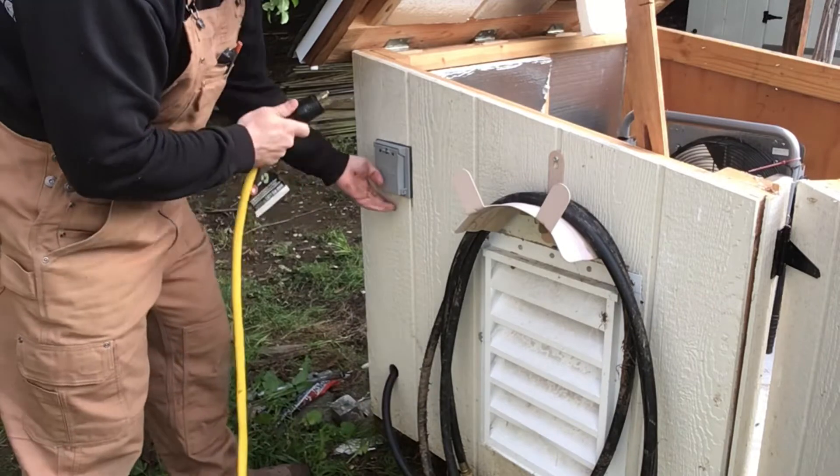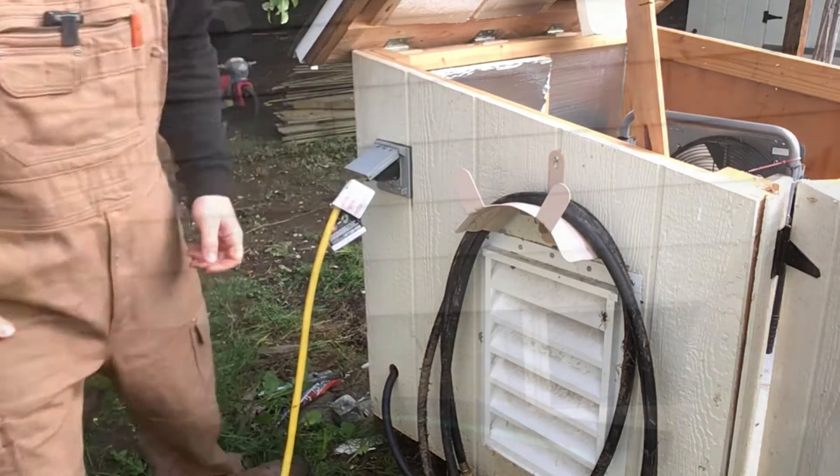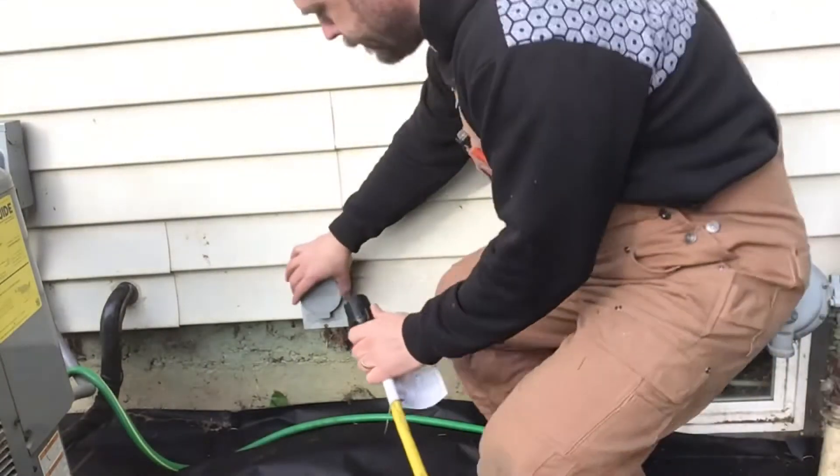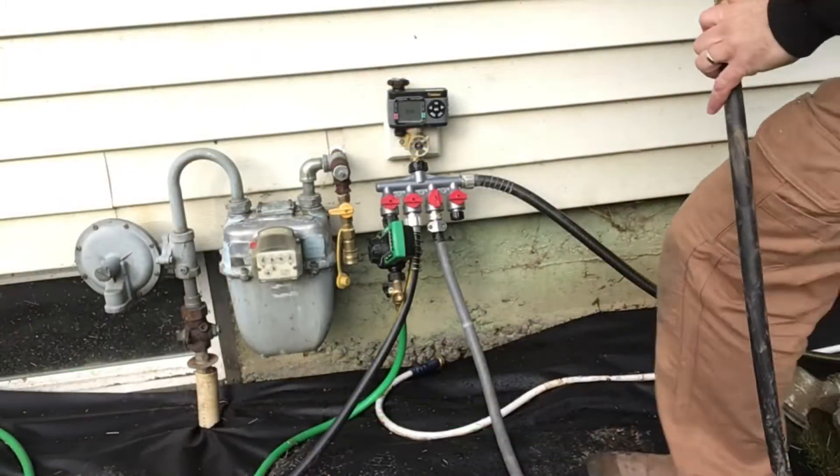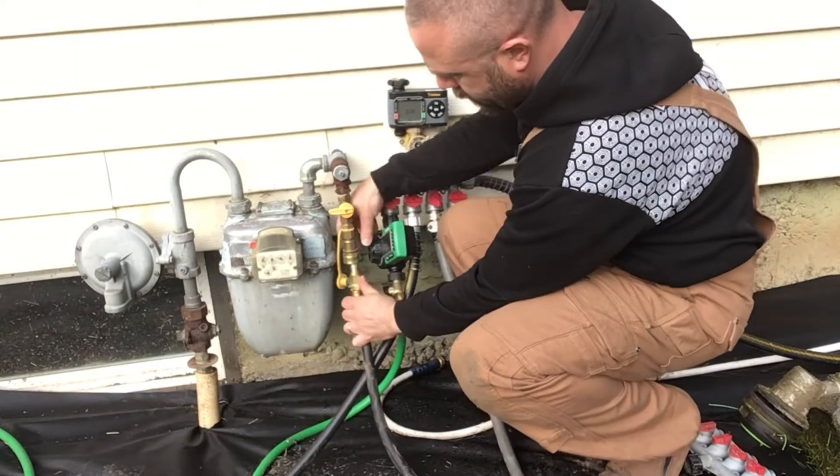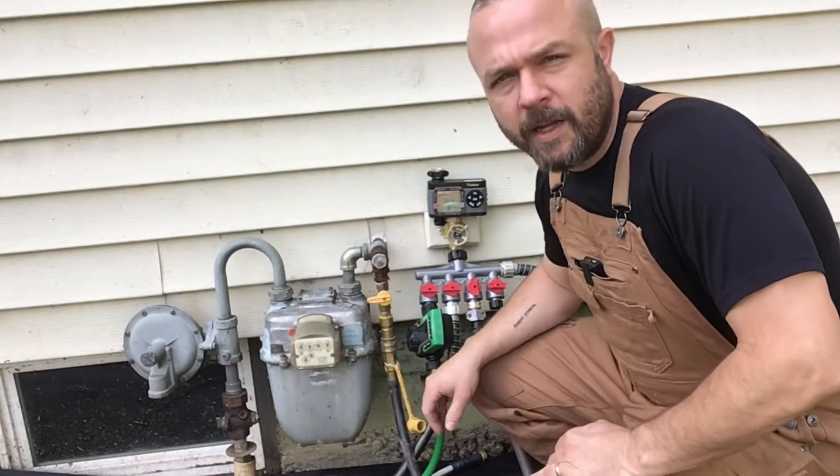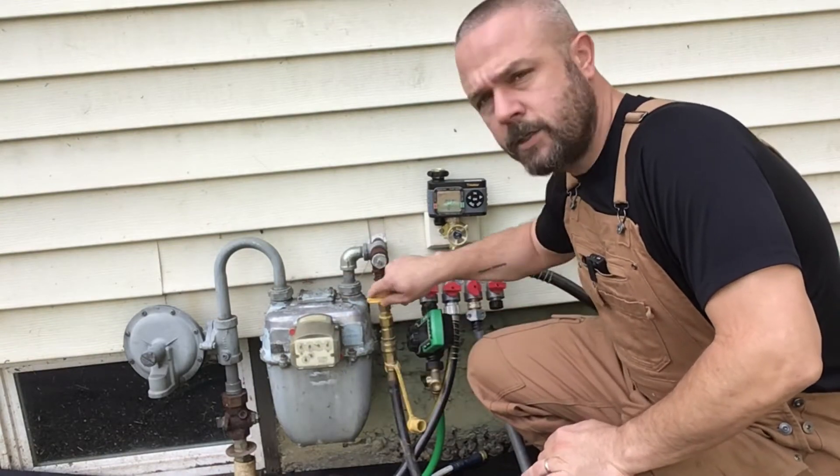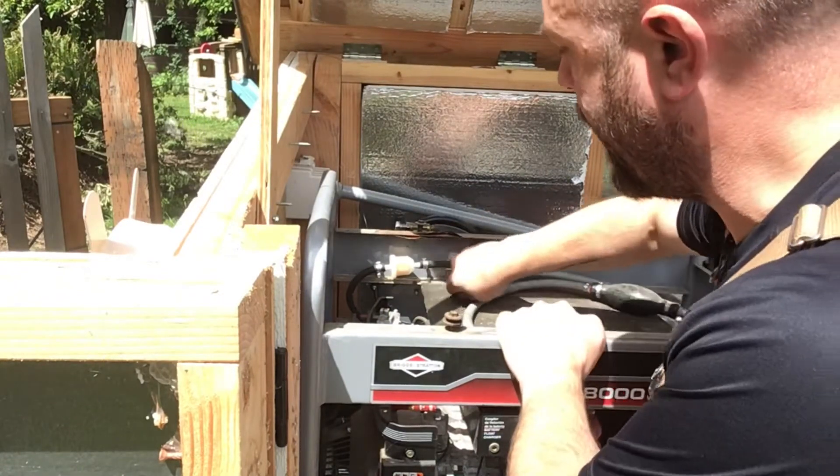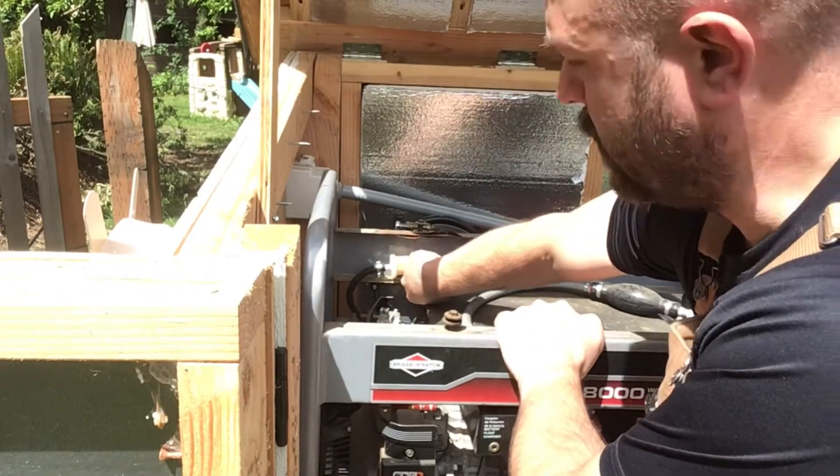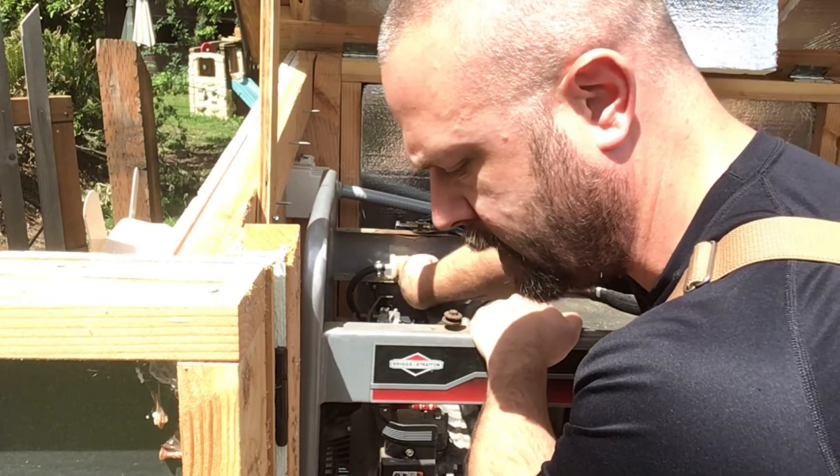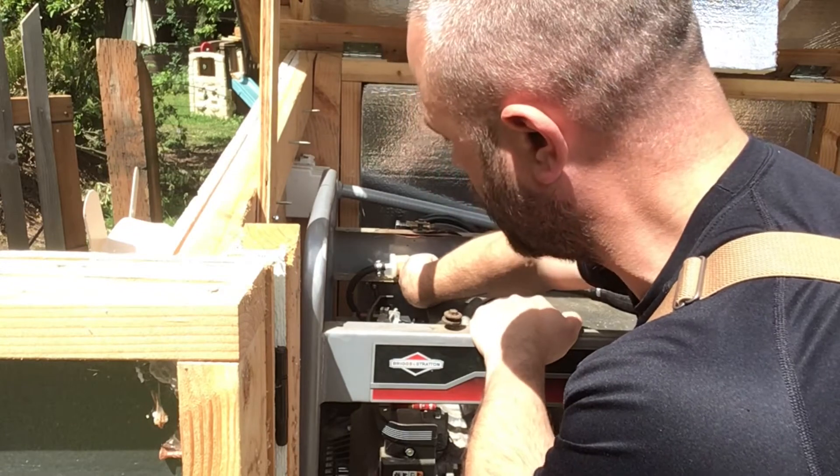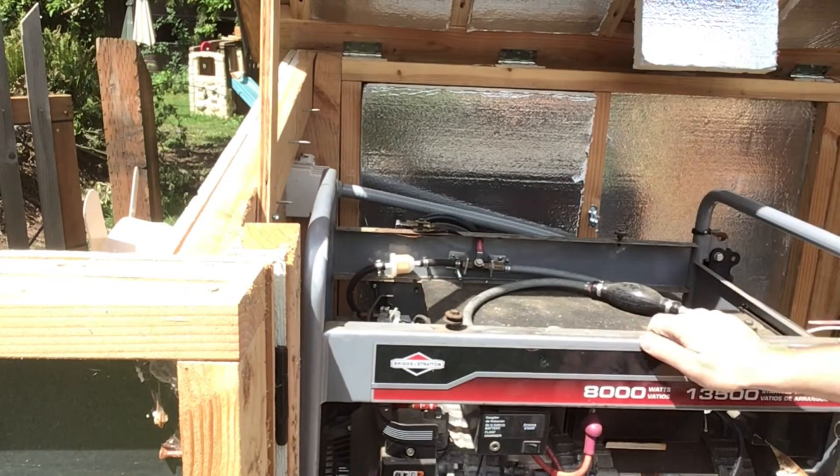First, we plug the cord into the outlet on the generator shed. Next, we plug the cord into the house. Last, we plug the gas into the gas meter. Now that we have the cord and the gas hooked up, we need to turn on the gas. Then come over to the generator and prime it with gas. On the back of the regulator, there's this little tiny button. You push, we can hear gas running. Let that go for about 10 seconds or until we can smell gas. Then give it a pull.